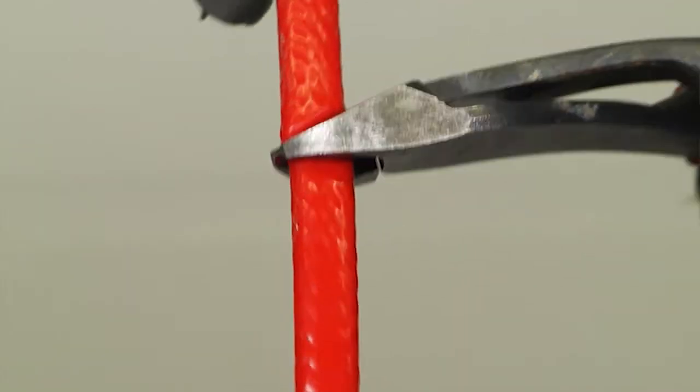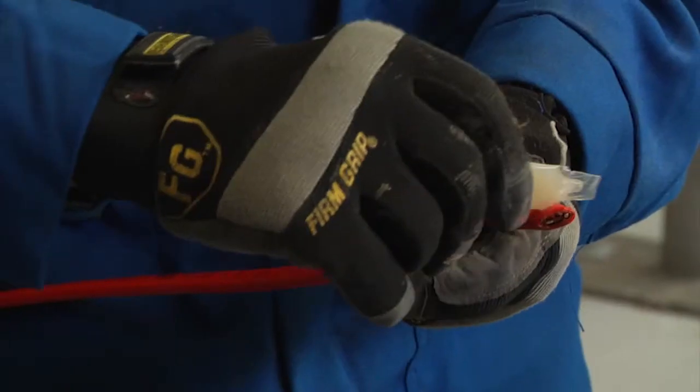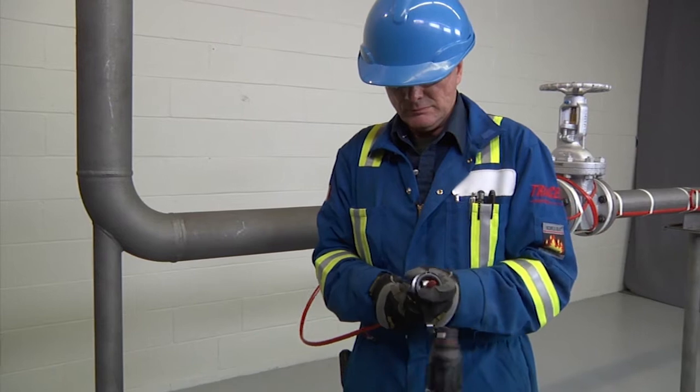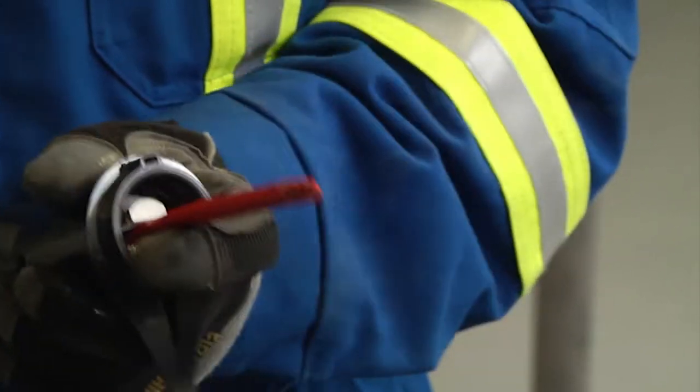Cut the cable end at a 45-degree angle. Apply lubricant for easier insertion into the gland. Insert the heating cable through the gland, leaving 12 inches, 300 millimeters of cable exposed.